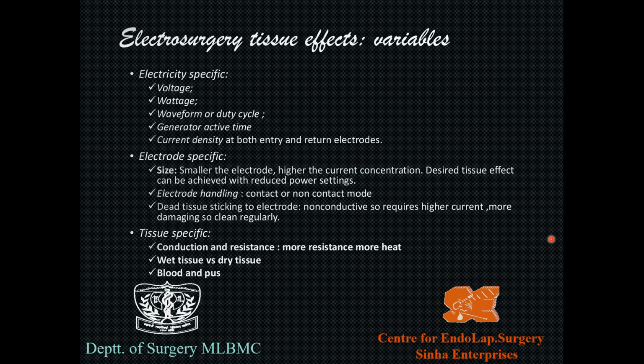So what is very important is, you must have seen when using the probe of the electrosurgical unit, on the tip of the electrode you have black attachments, the sedimentation. You have to rub that and remove it. This is nothing but the dead tissue sticking to that probe, right? Then the current cannot pass anymore. Once you clean it, the current starts passing again. You must have seen that when you're using an electrosurgical unit.